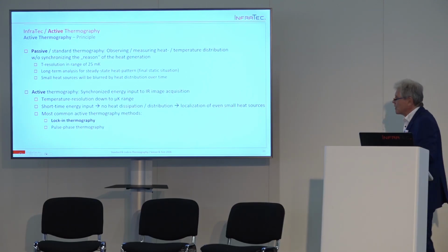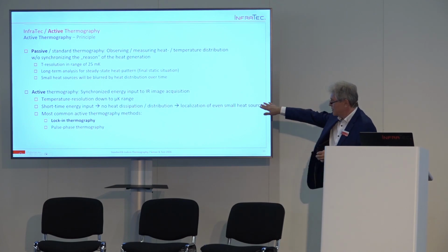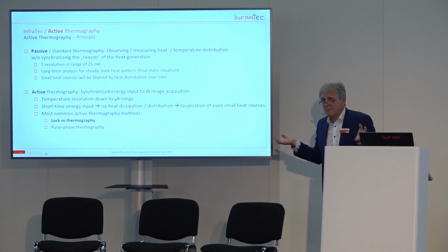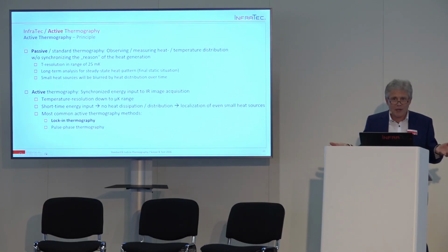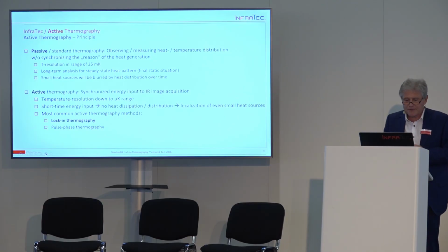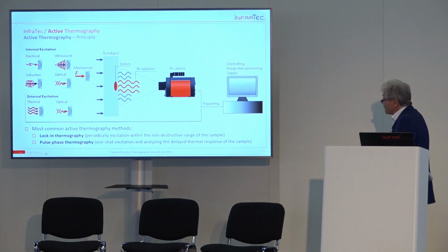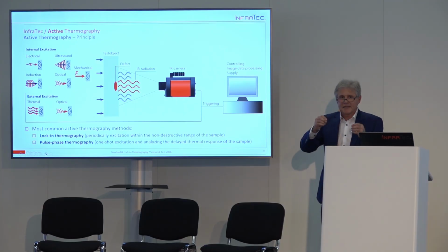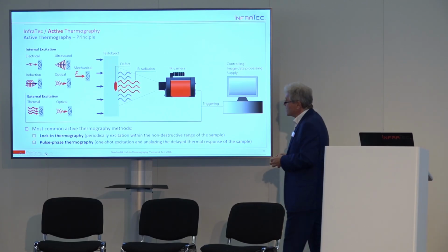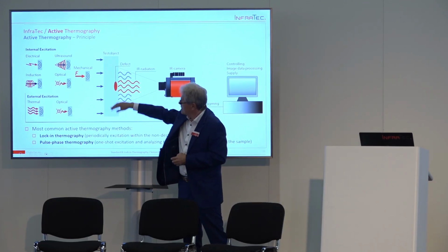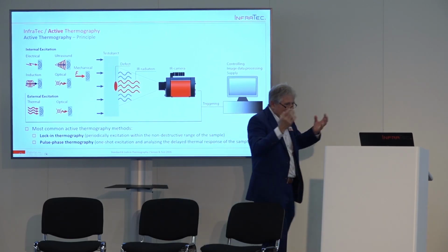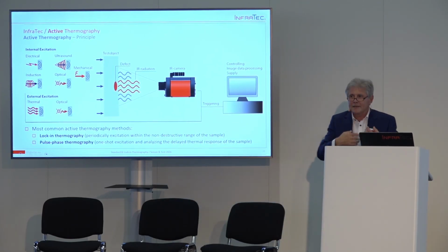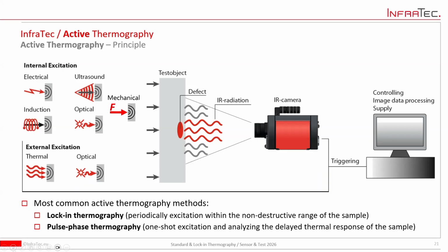There can be a short energy input with no heat distribution, or it can be done with a tool called lock-in thermography. Okay? Or pulse phase thermography, but for electronics it's mainly lock-in thermography being used. For standard materials, let me say for standard metallic material probes and for other probes, what are you doing? You have a test object, and then maybe you have a test object with a defect inside it, or a material inhomogeneity inside, but you don't see it on the top. So with the standard thermography, you cannot see anything. You don't see the fault.